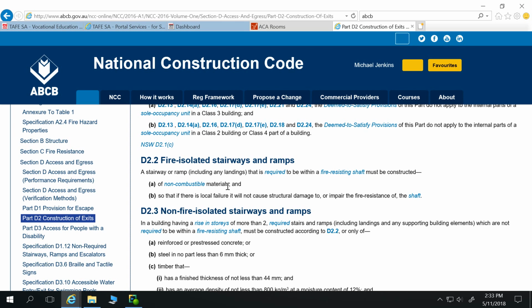What we don't want is, say, steel I-beams that run through here to another part of the building, and then we have a fire in there. Our steel I-beam wants to do that and starts breaking down this section of wall. We want to ensure that our construction elements are autonomous, mounted in such a fashion that if that burns away or melts, it can collapse without taking chunks out of our fire isolated stairway, or opening it up to the fire.